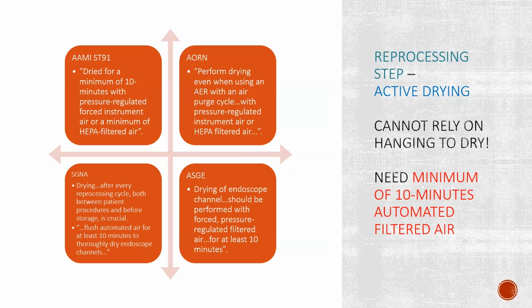One of the more noticeable changes to all 4 standards and guidelines is the emphasis on active channel drying post-AER. In unison, all organizations call for a minimum of 10 minutes with automated filtered air. This needs to occur after the AER. The AER cycle is a purge only, not a validated drying cycle. Active drying is required whether the scope is headed right to another procedure or to storage.